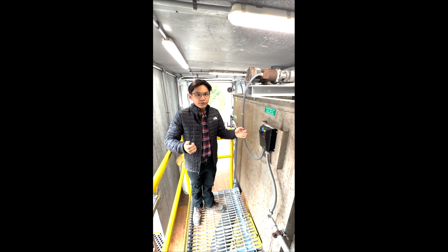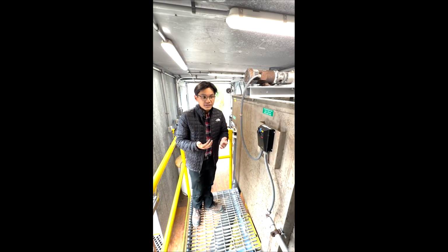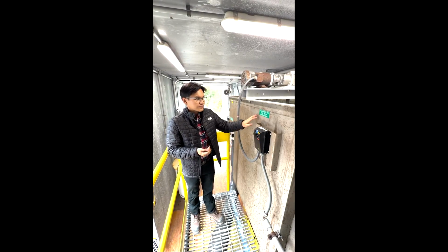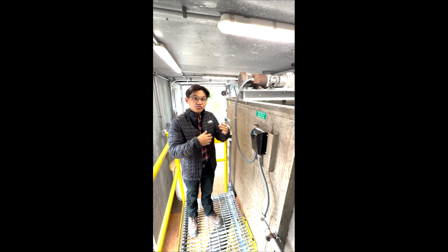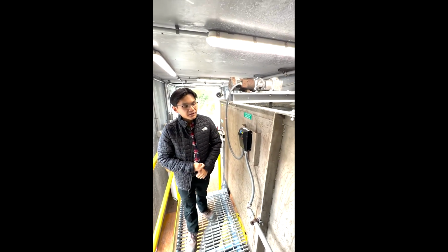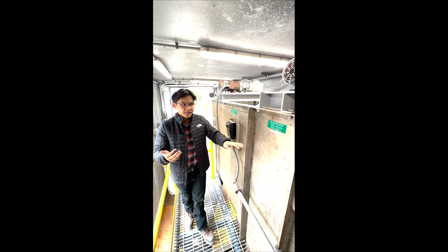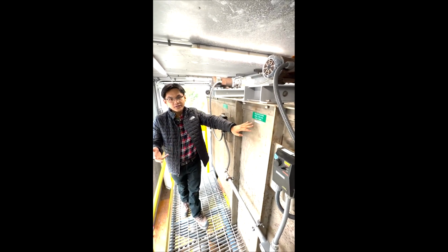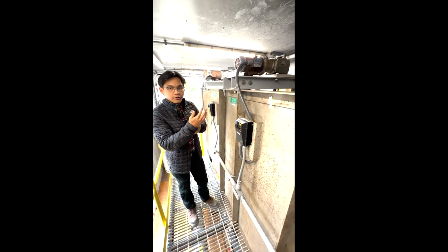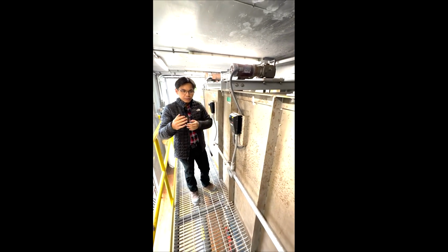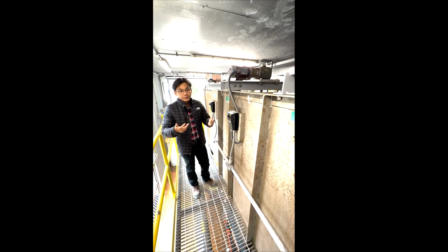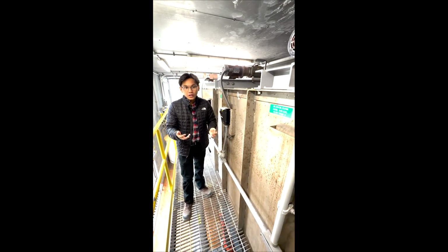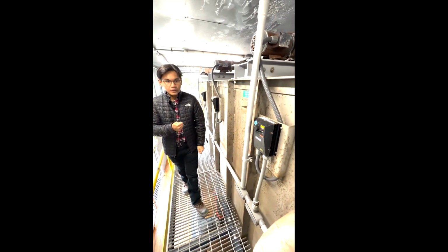Once we're done with the chemical dosing, we have a series of tanks that we're feeding the water through. This first one is a rapid mixing tank to distribute the chemicals evenly. Then we have a series of other tanks, floc tank 1 and floc tank 2. These are a gentler mixing so that the particles can really come together and form flocks. Now, what exactly is a floc? Well, we'll see it further down.